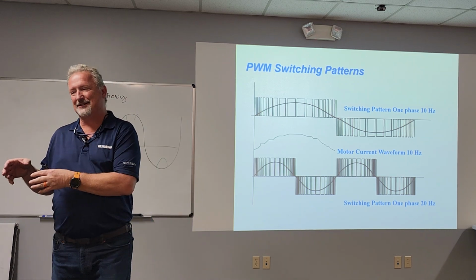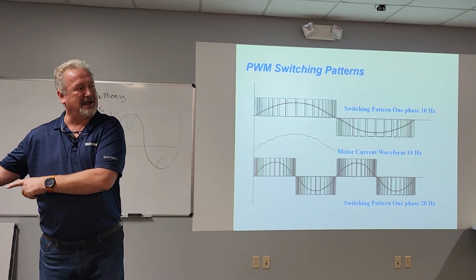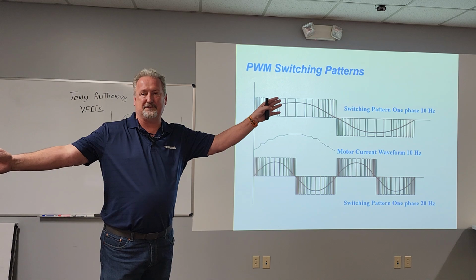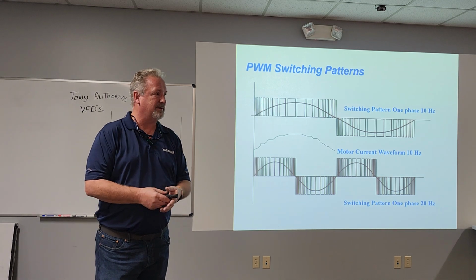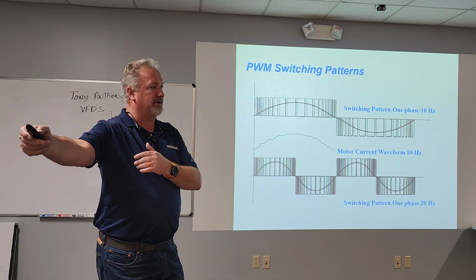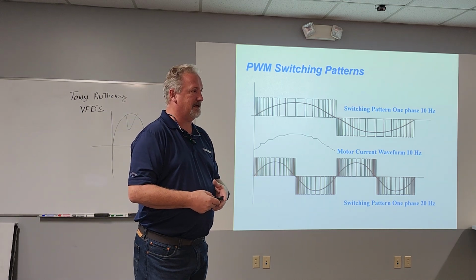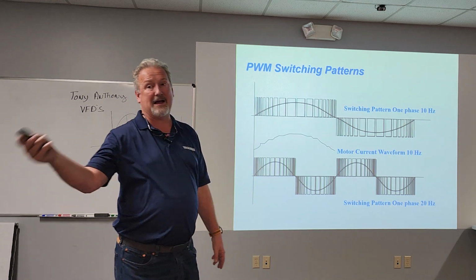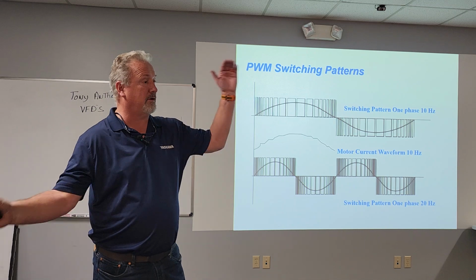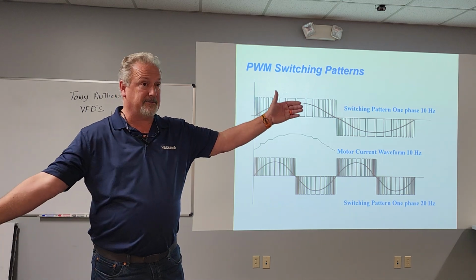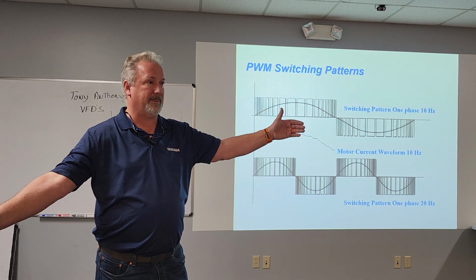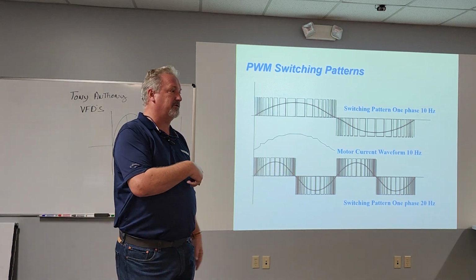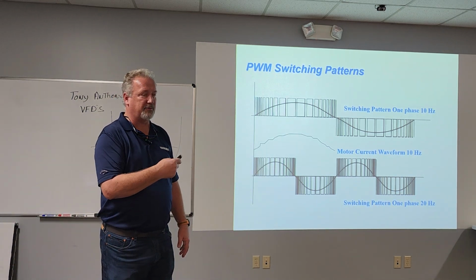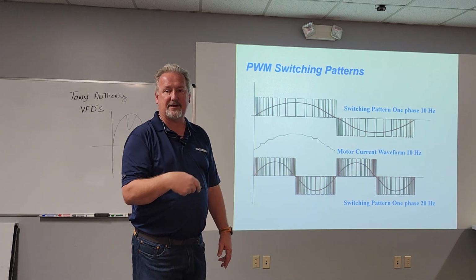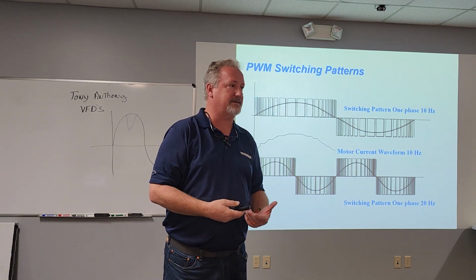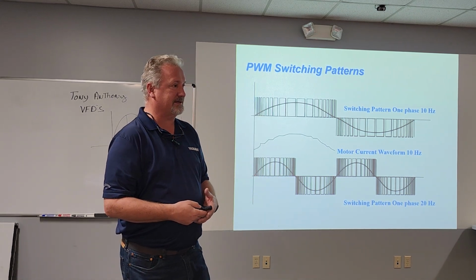And the way DC works, the further that motor is from the drive, the more those pulses grow. So those spikes will get worse. So if you're 100 foot from the motor drive, it may be 1200 volts. If you're 10 foot, it may be 1100. You're at 500 foot, you may be 1500 volts peak to peak. That peak to peak, that's extra heat. That's why you've got to make sure you have the right equipment or the right motors to handle this extra heat that we create because we're pulsing DC to the motor. We're not just sending a pure AC to it.